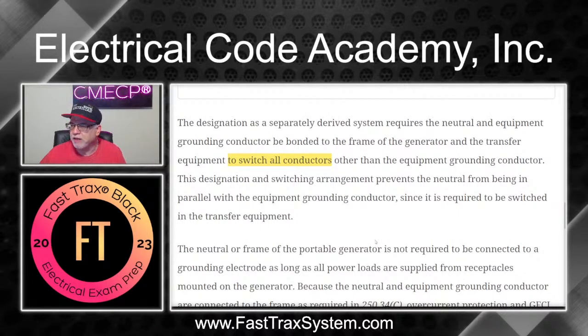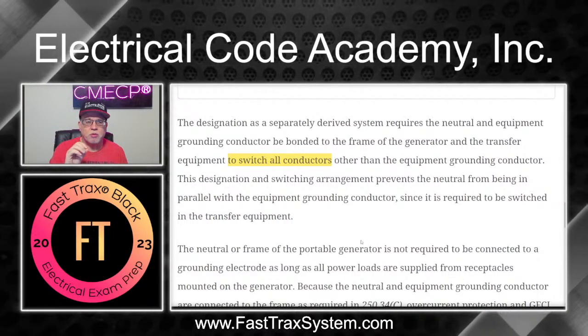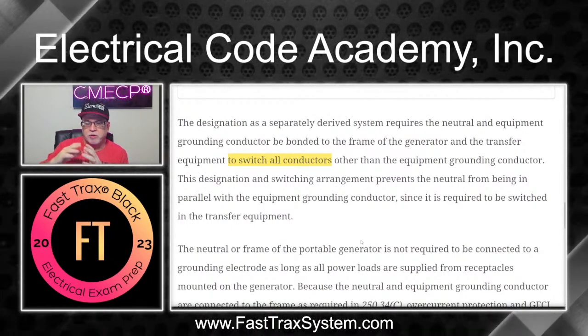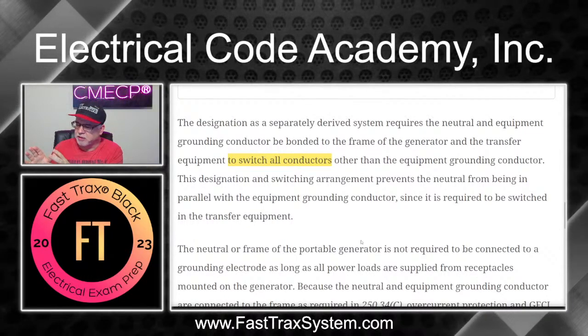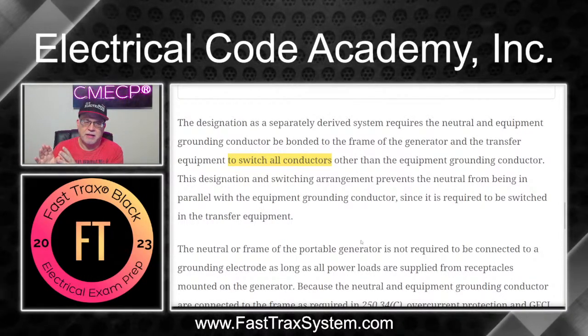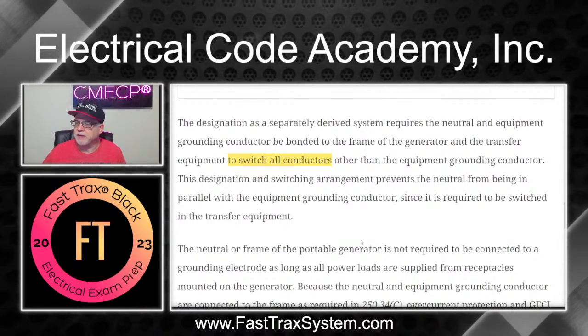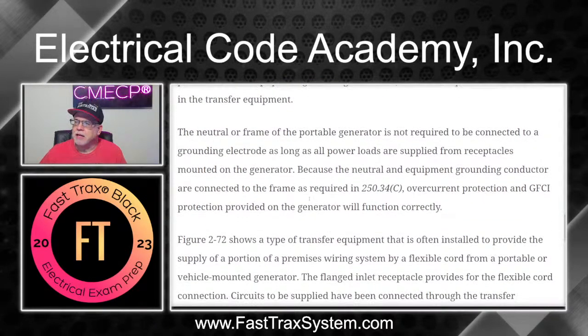I'm going to make sure that we at least hammer that home: switching of the neutral is very important in determining whether or not your generator is separately derived or not, okay? It plays a critical role in that. Now let's talk a little bit more.